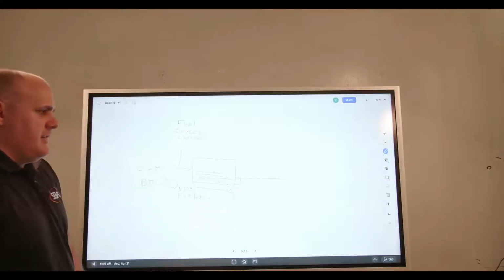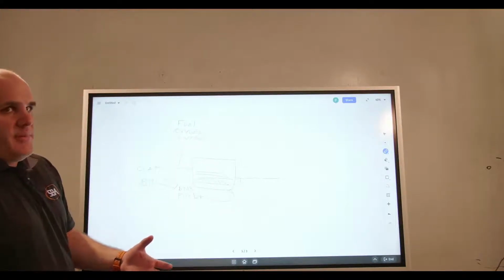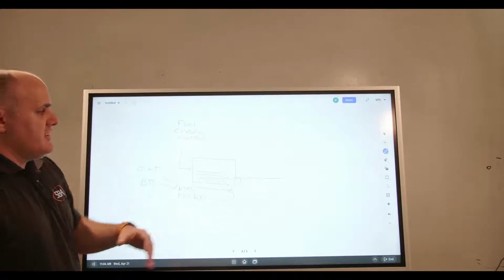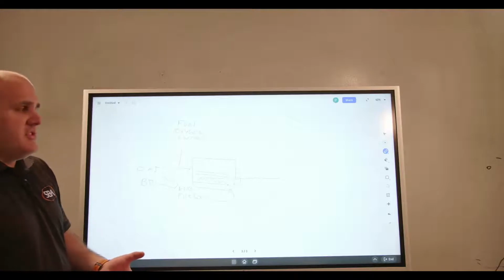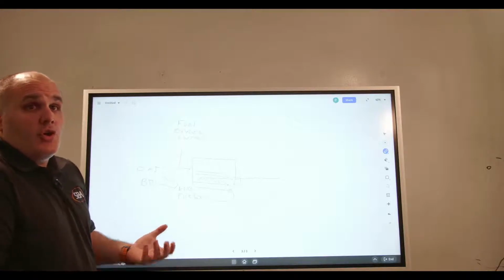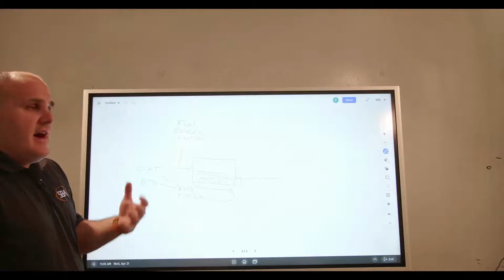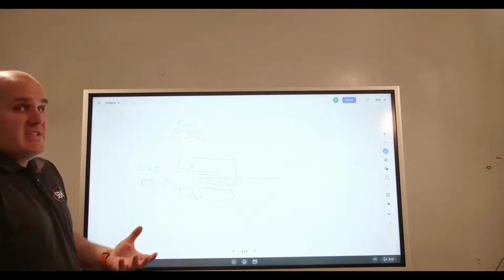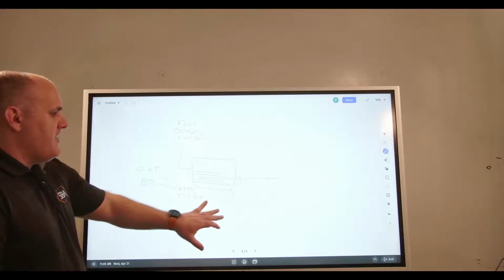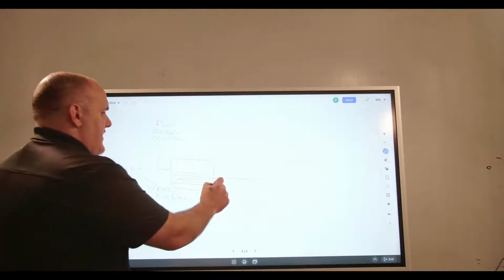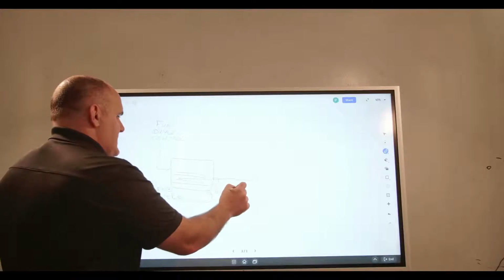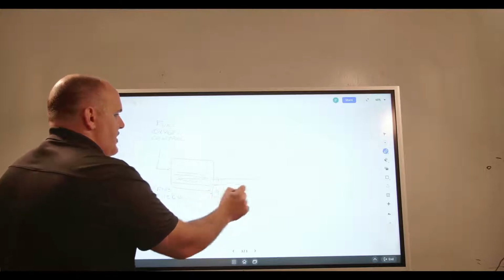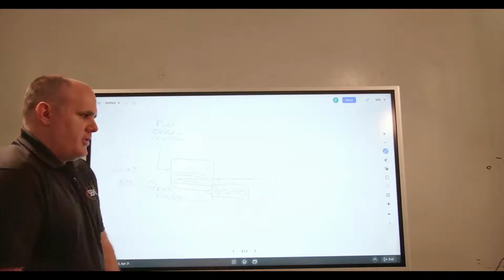Now, I'm not going to get into BACnet and all of the Modbus integrations and BACnet integrations that we'll see with boilers potentially. Most of the time in the world I grew up in, we used a 0 to 10 volt signal, or we used a 0 to 135 ohm signal that would basically adjust and would reset our fire rate. Our primary fire rate is typically going to vary between 160 to 190 degrees, right in that area. And then our secondary rate, which we'll talk about, will look a little differently.